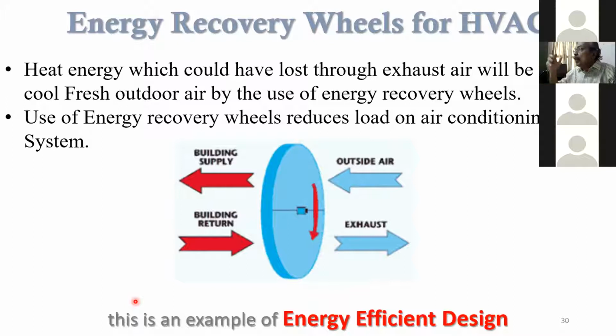So if you can recover that coldness from the exhaust air and transmit it to the warm fresh air coming from outside, you are taking advantage of the energy which is recovered from the cold air. This is achieved through an apparatus known as energy recovery wheels for the HVAC system. Heat energy which could have been lost through exhaust air will be used to pre-cool the fresh outdoor air by the use of energy recovery wheels. Use of energy recovery wheels reduces the load on the air conditioning system. So that's the correct move in energy efficient design.